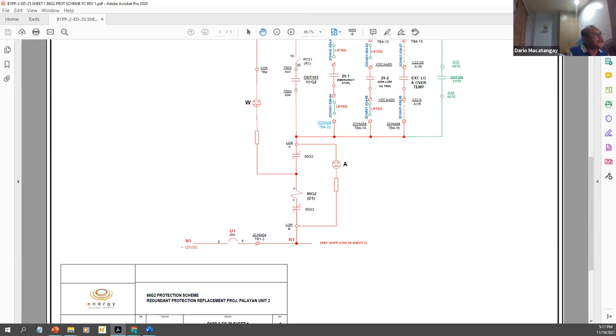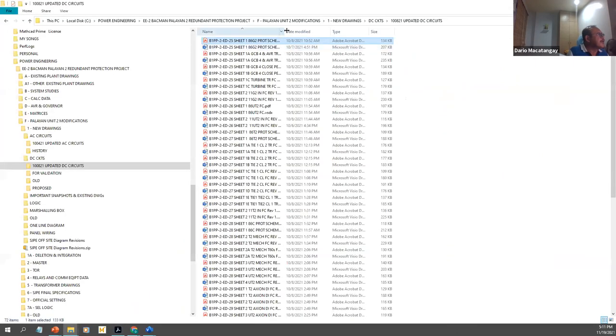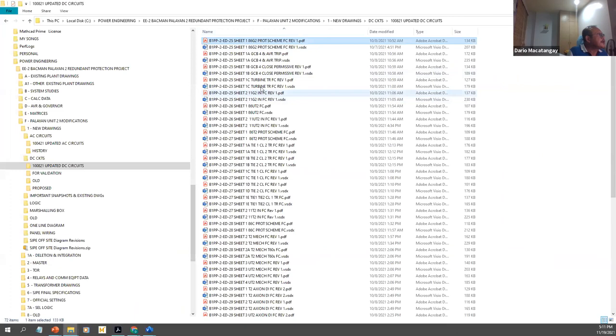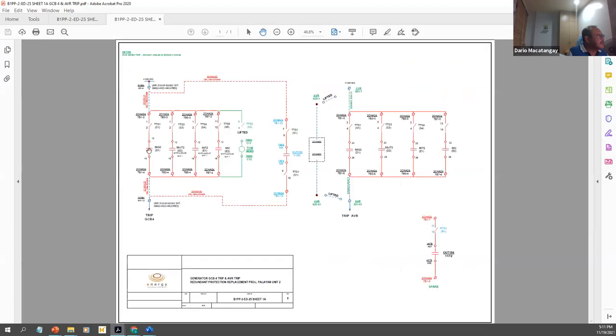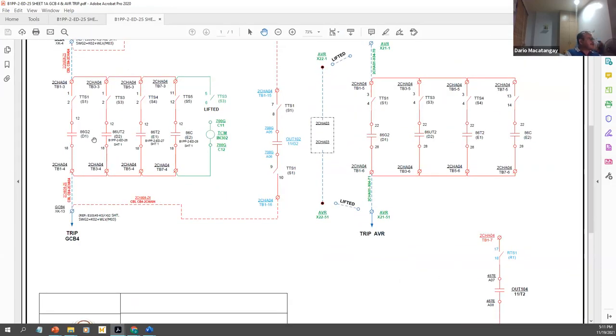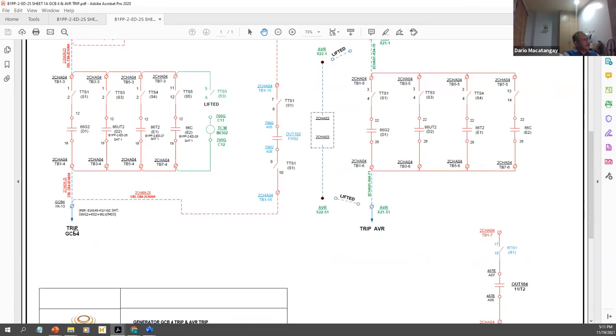So we need to open up another drawing again, which is actuated by 86G2. So we go to the generator trip, which is this one. Okay, so here, this one here is an 86G2 contact. So when it closes, it trips the GCB4, and that GCB4 goes to the trip coil. Then the generator breaker has its own elementary, which has those trip coils associated with it. So you need a relay to trip a breaker. That's the whole meaning of it. Is that clear? Am I clear?